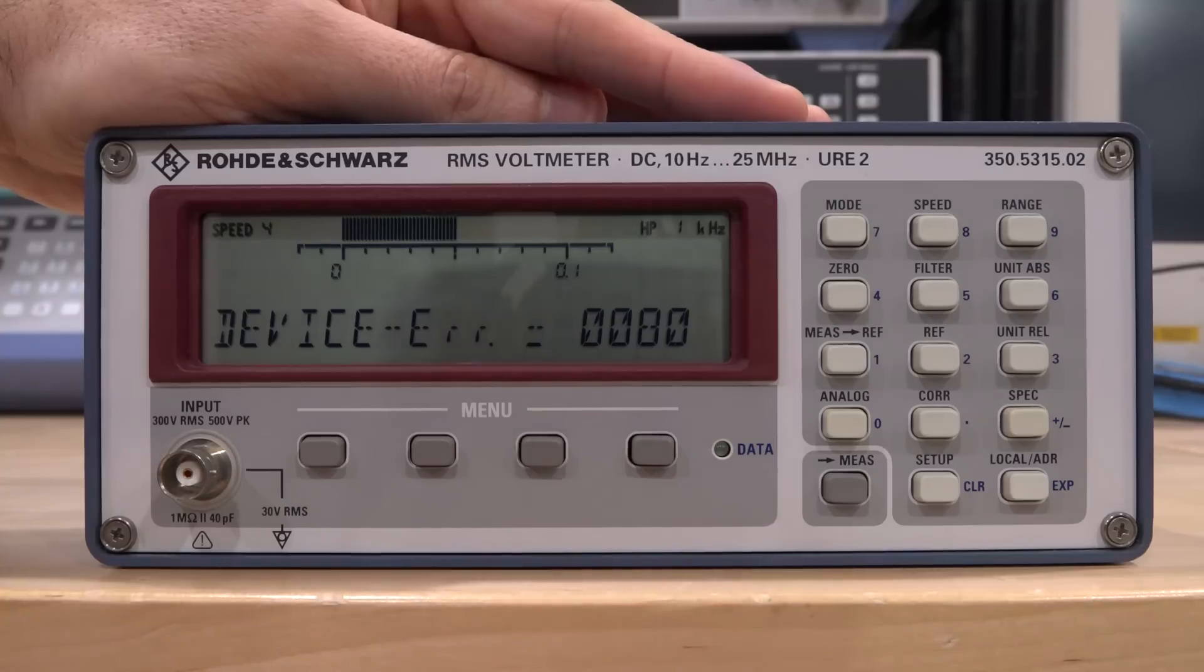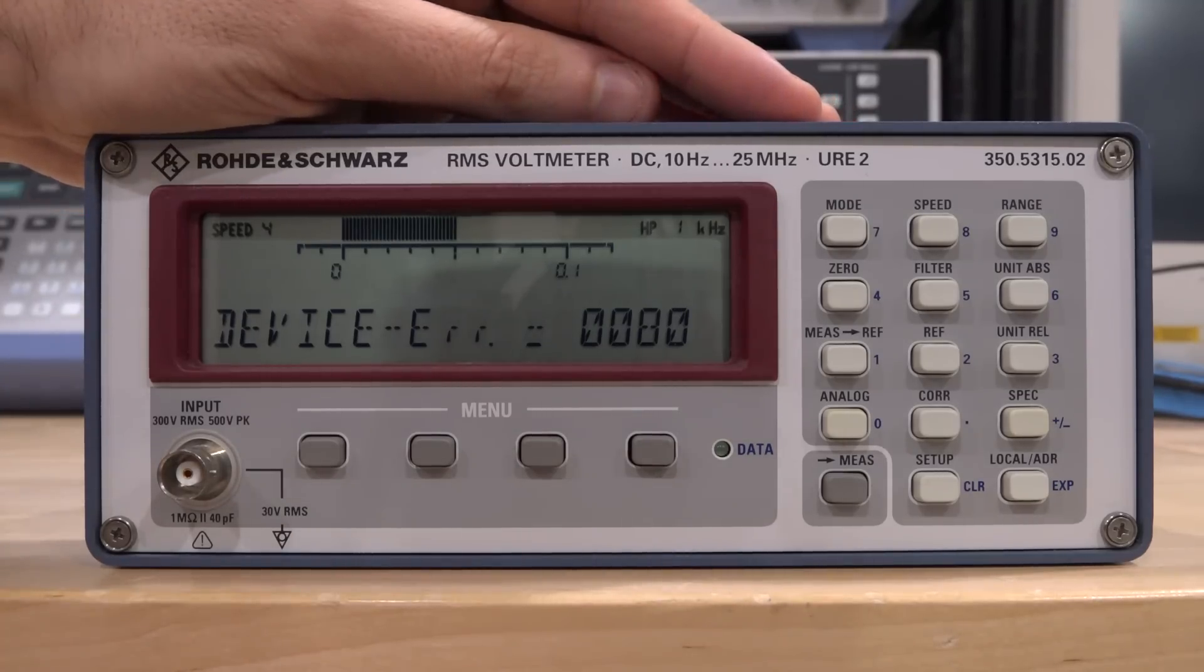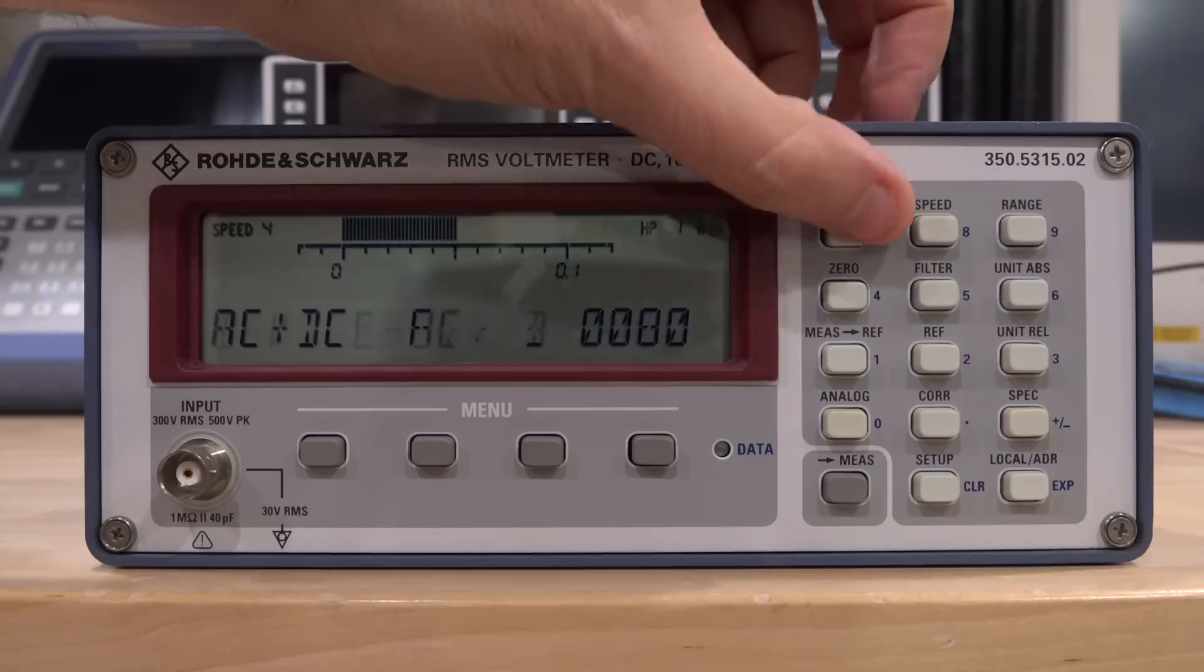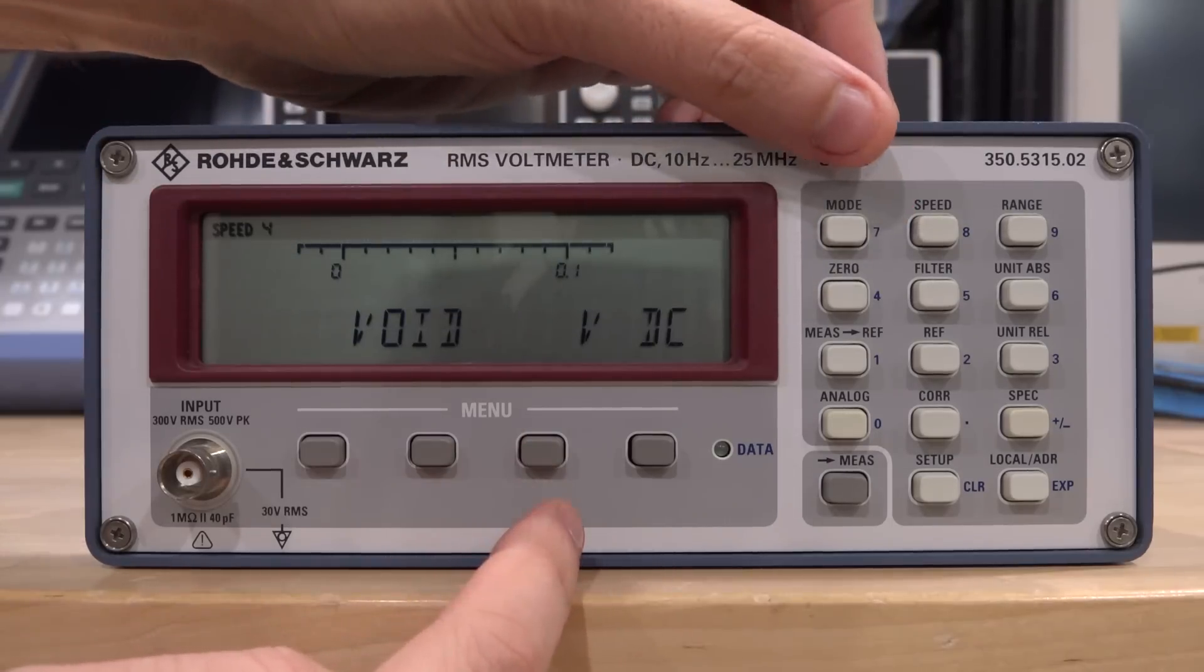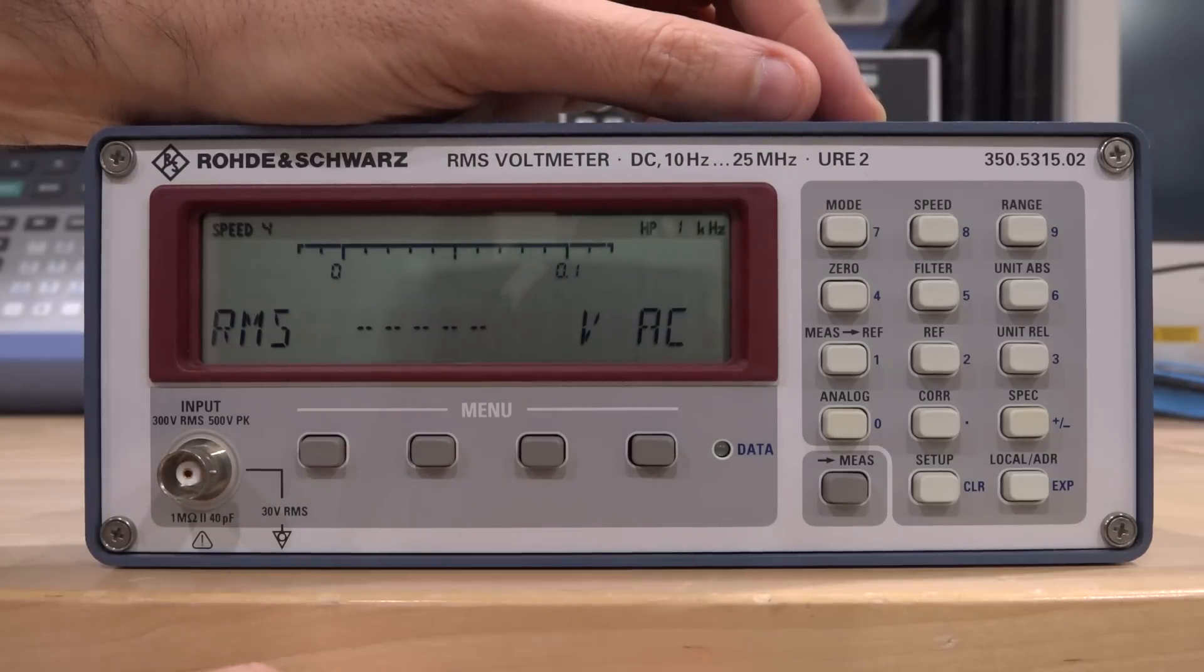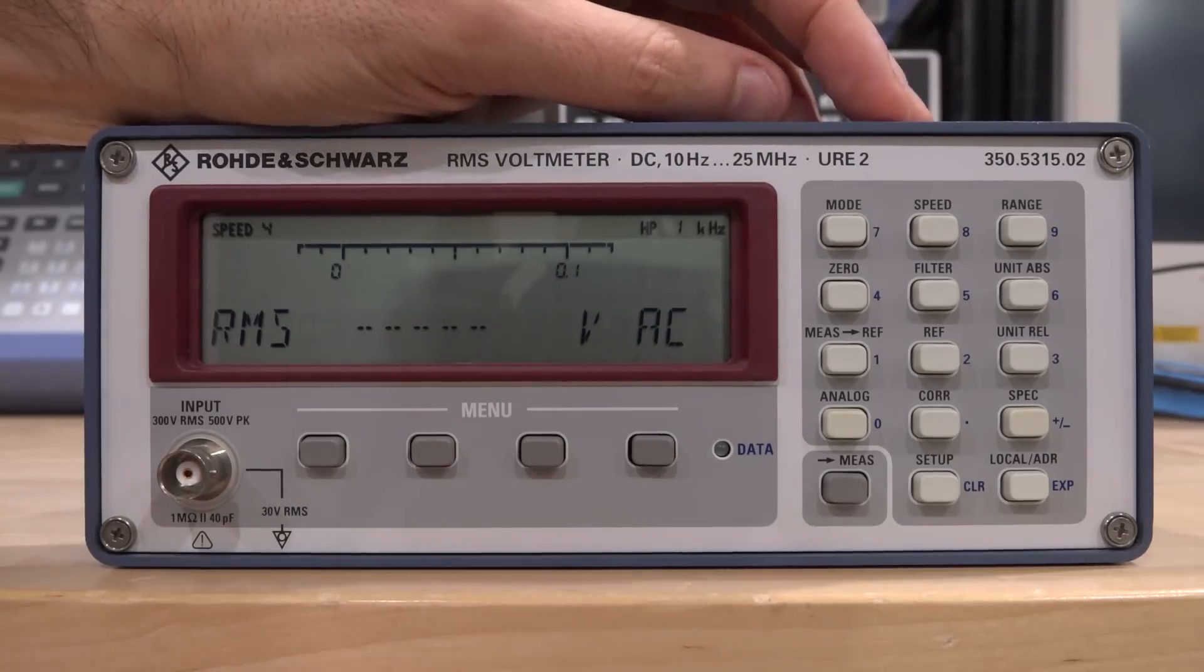This error shows up every once in a while but not always, which means the problem is intermittent. When you turn it on and off, you can hear all the relays clicking. More importantly, when you select DC or only AC, I can hear relays click internally, so it's switching things on and off. Let's quickly try this and convince ourselves that there is a difference between the AC and DC path measurements.